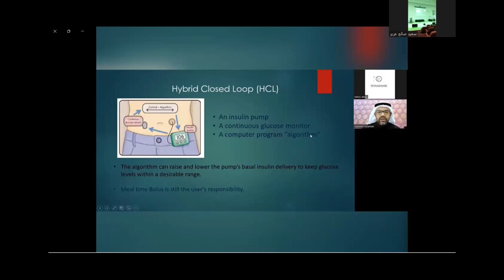So what is an advanced hybrid closed loop system? It consists of an insulin pump, and this insulin pump will have settings where the healthcare provider can adjust it based on the patient in front of them. And then a continuous glucose sensor, and this continuous glucose sensor will be communicating with the pump with an algorithm. This is what is really making the difference in this advanced hybrid closed loop. This algorithm is different between different companies. For example, the one used in Medtronic is called PID, or Proportional Integral Derivative controller. The one used by Omnipod or Tandem or Beta Bionics is called MPC, or Model Predictive Control. And those differences are basically differences in the algorithm itself.